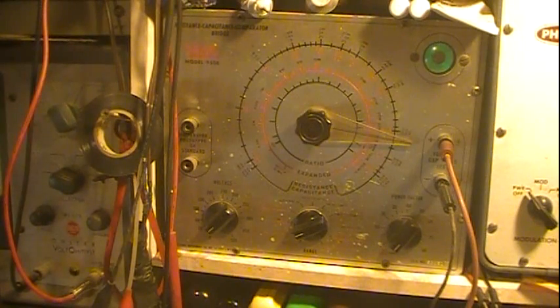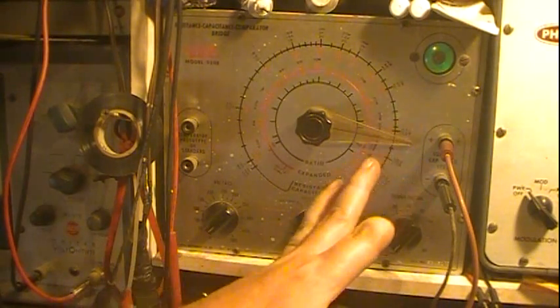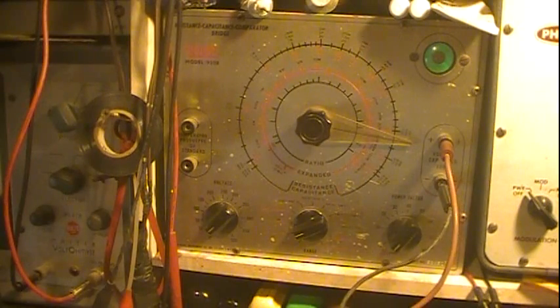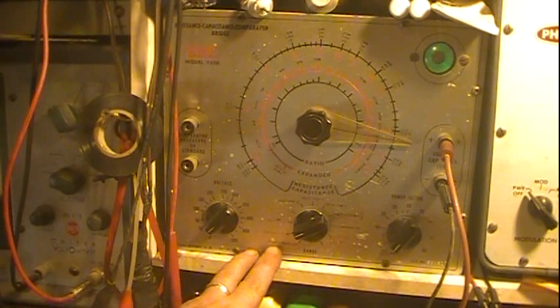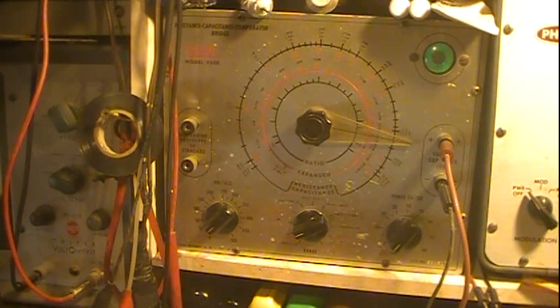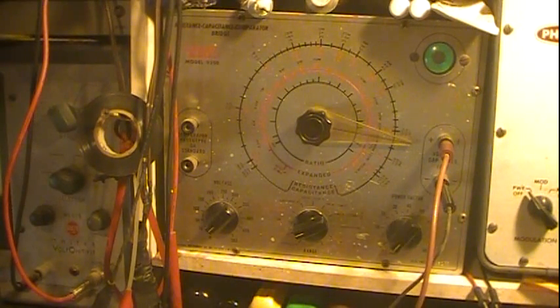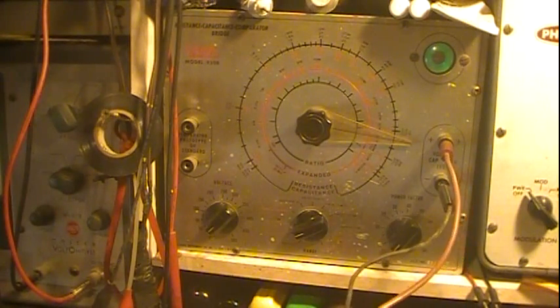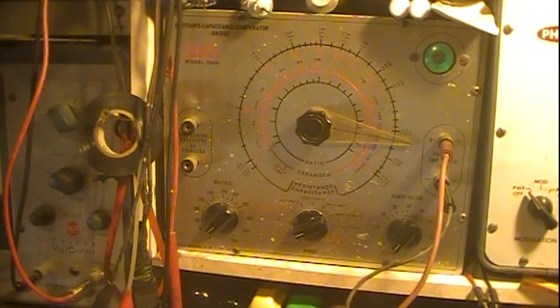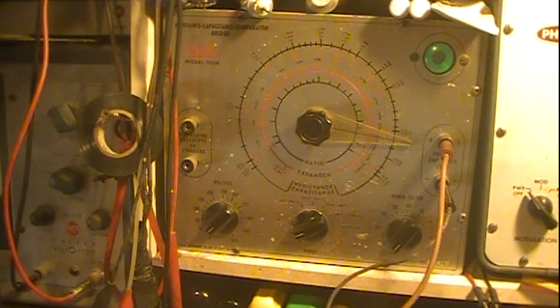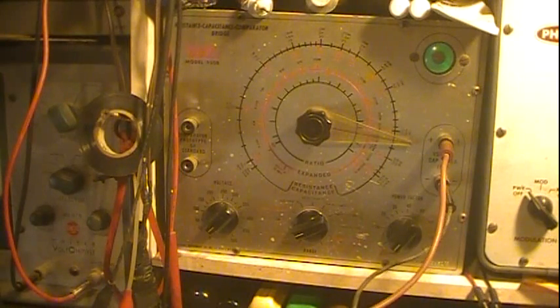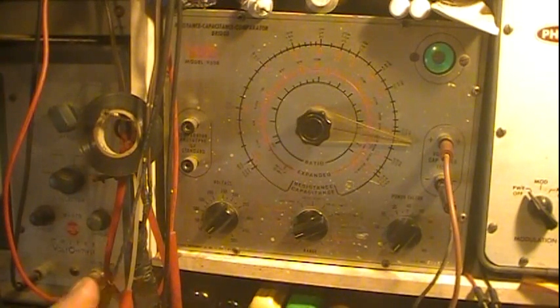Now, one thing I do want to point out on these, the one thing I can definitely add, you have leads, okay, but these testers will test down in the picofarads. In fact, this one goes down to 10 picofarad. When you're doing some small values of that nature, these leads will cause you all kinds of headaches testing the capacitor. Not so much on the leakage, but if you're actually looking for a value or seeing how close it is on value, because when you get down there, the leads themselves will create a capacitor in themselves. They're capacitive coupled, so that'll actually throw off the capacitance.